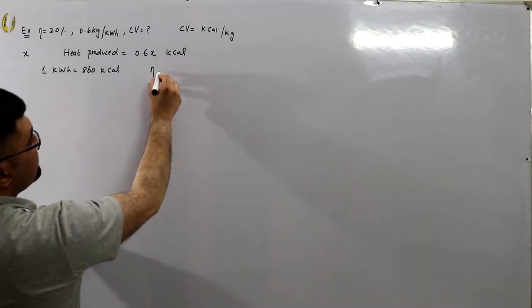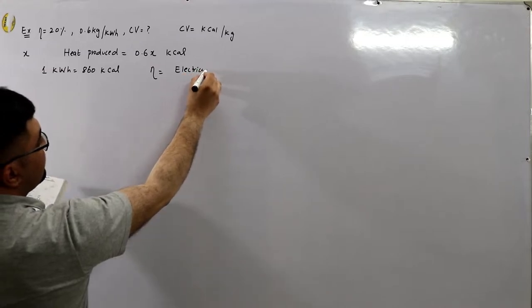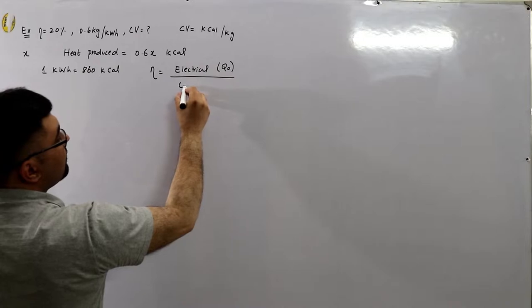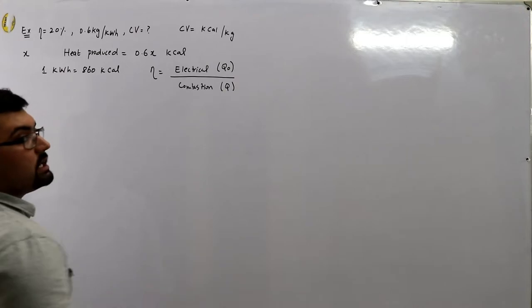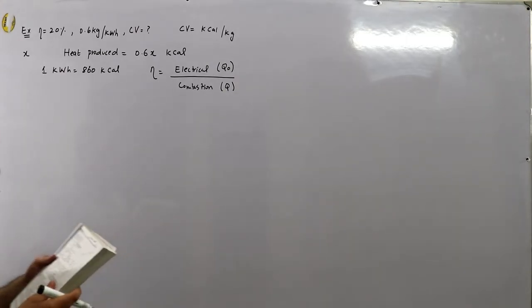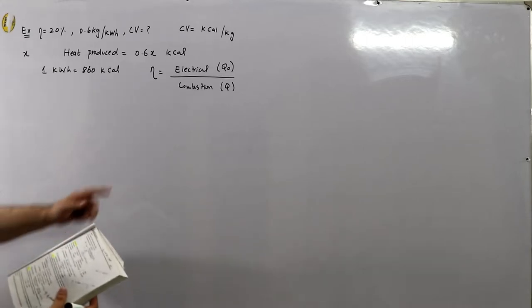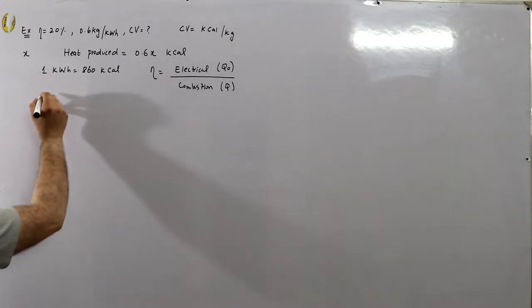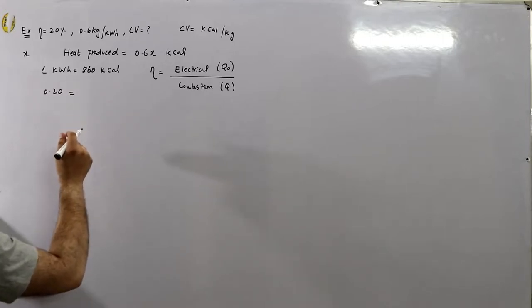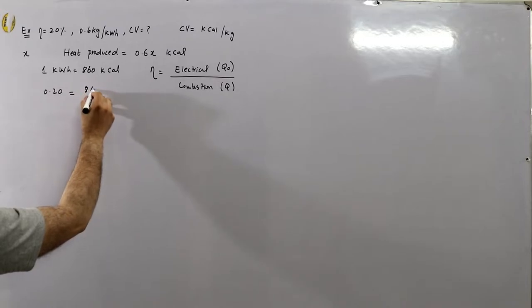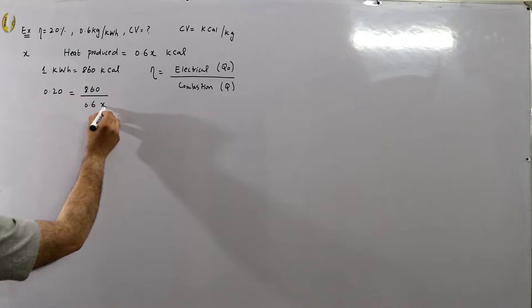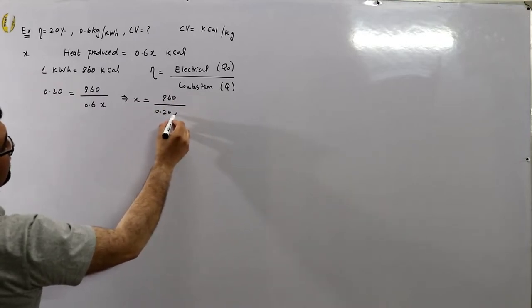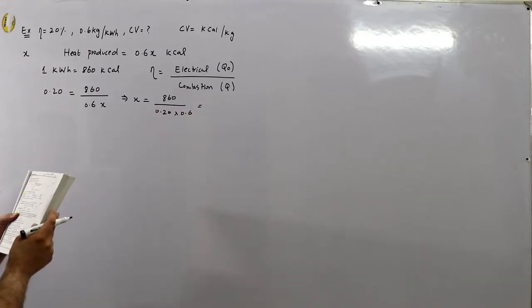The overall efficiency is the electrical output in heat units divided by the heat of coal combustion. So eta = Q_out / Q_in. Here eta is 0.20, the electrical equivalent is 860 for 1 kWh, and Q_in is 0.6X. Therefore X = 860 / (0.20 × 0.6), and the calorific value comes out to be approximately 7166 kilocalories per kilogram.